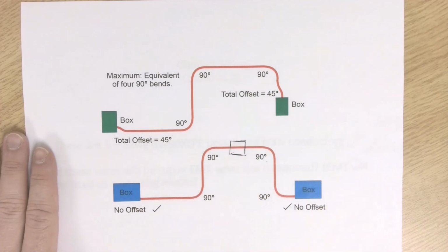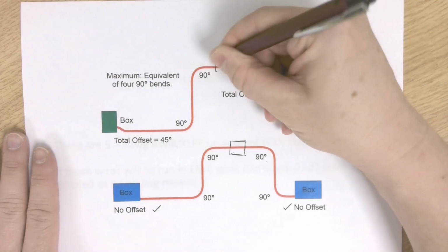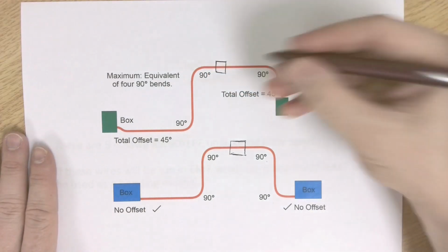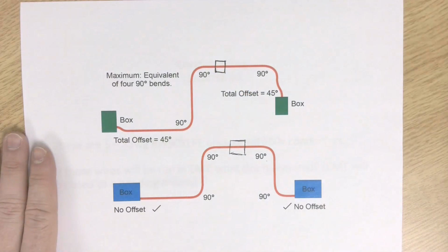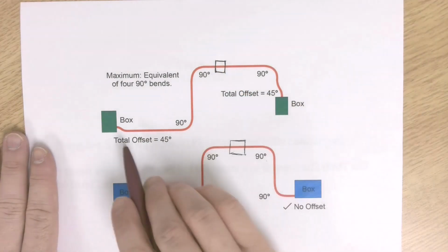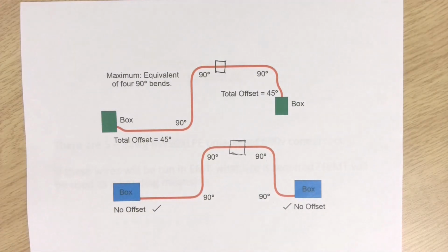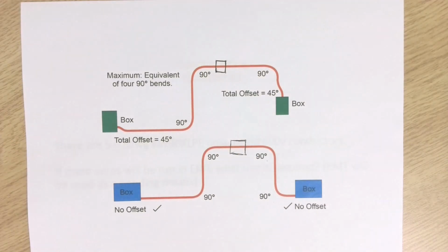Now, I'm going to say for both of these runs, from personal experience and struggles, there should definitely be a box midway through for both. You don't have to. It would be exceeding code. Maybe you also take these down from 45 degrees, do 10 degrees, spaced a bit farther apart. But anyway, how you bend conduit and tubing is basically field knowledge. So when you get the chance, make sure you learn. It's a very useful skill.